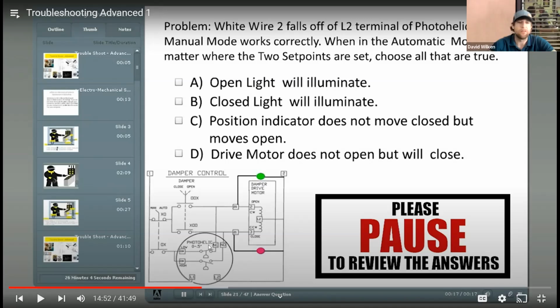I think what happens is this is normally closed and there's 120 volts here when you're in auto. So that's going to be shooting right through because the switch isn't going to change states. So that normally closed contact is going to go directly to open. I'll agree, Dave. So you're gonna always have power to your open side. So C is correct.